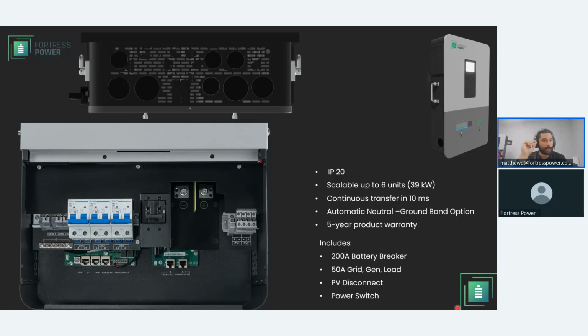It comes with a power switch button on the right side of the inverter. It comes with 3 50 amp AC breakers, so that would be breaking the grid, gen, and load, and then a 200 amp battery breaker, okay, just right here. This is the 3 50 amp AC breakers, 200 amp breaker, your PV input right here, 2 MPPTs, positive and negative on PV1, negative and positive on PV2, okay?